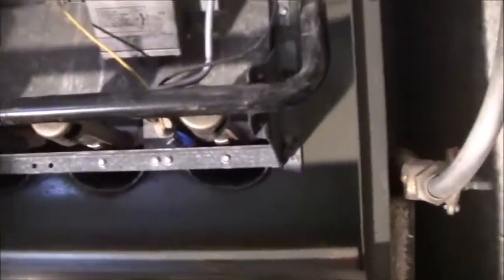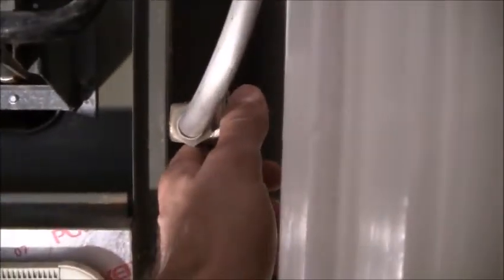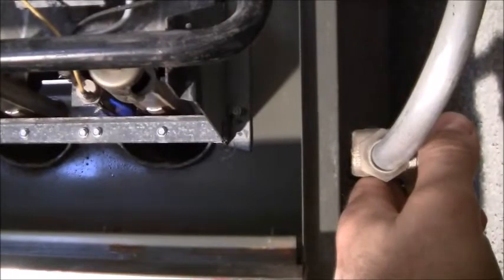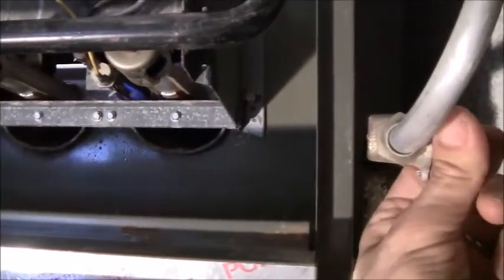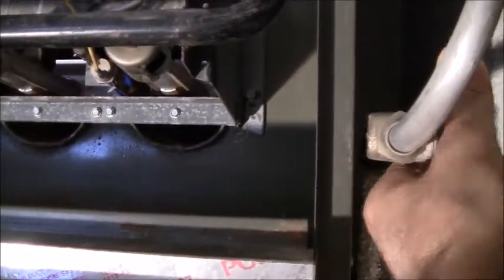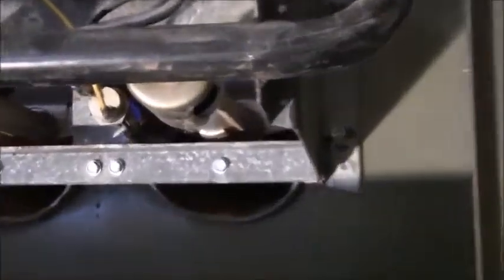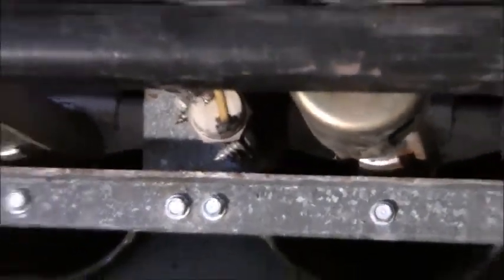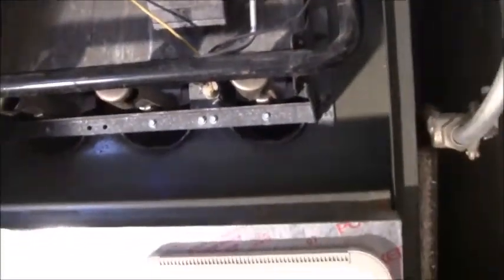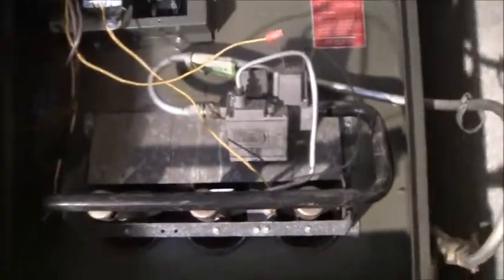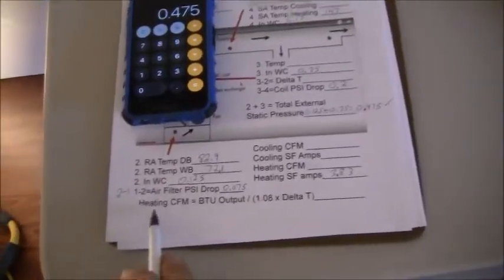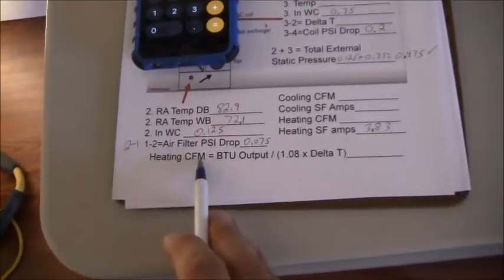Because this is still summer, I don't need the pilot, so I'm going to go ahead and shut the pilot off. So I'm going to shut this valve off there, and you'll see the pilot shut off. There's the pilot flame, and the pilot flame just shut off. We don't need the pilot because it's the summer. I'm just doing this as testing, okay? Now let's figure out the heating CFM.